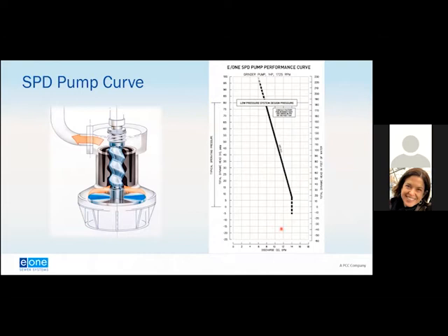Now, if we were looking at a truly positive displacement pump conveying, say, a sludge product, some mixed liquor suspended solids or something like that, or any fluid that had a higher viscosity, this pump curve would probably be a little bit more vertical. But because we are conveying a liquid, we do have that slip. So we do have some variance that if you do have a higher pressure, you are going to get a little bit more slip through this cavity than you would with water. But it is essentially a near vertical curve that, with very little variation, regardless of what the total dynamic head is in the system, you're not going to have as much variance on the discharge point of the curve.